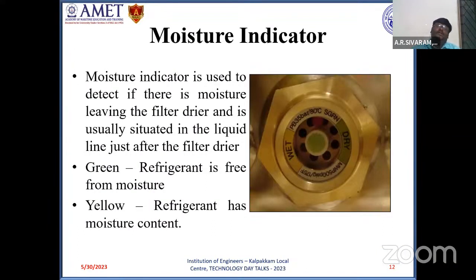Coming to the moisture indicator. At the filter dryer outlet, there will be a moisture indicator. Of course, this is present in commercial systems. This moisture indicator indicates whether the filter dryer has removed the entire amount of moisture or not. If the moisture indicator indicates the presence of moisture, then the filter dryer, or the desiccant present inside the filter dryer, needs to be replaced. Here, the green color indicates the refrigerant is free from moisture. It is completely dry. And yellow color indicates that there is moisture or water vapor content present in the refrigerant. The filter dryer has not completely removed it.